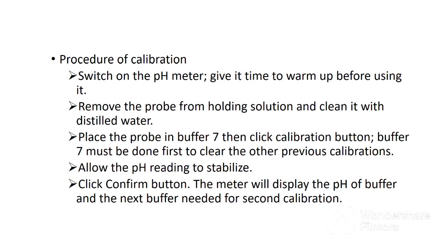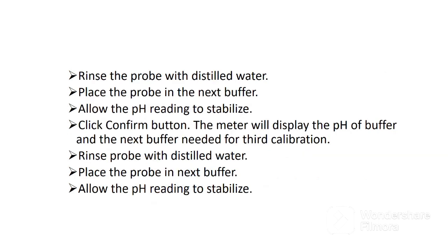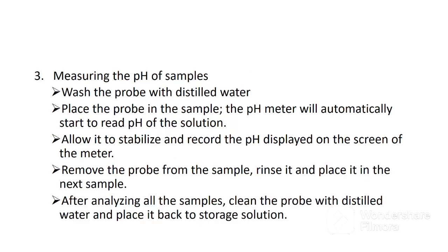Rinse the probe with distilled water. Place the probe in the next buffer and stir gently. Allow the reading to stabilize, then press the confirm key. Again, rinse the probe with distilled water. Place the probe in the final buffer solution and stir gently. Allow the reading to stabilize and press the confirm key. The third stage is to measure the pH of samples.